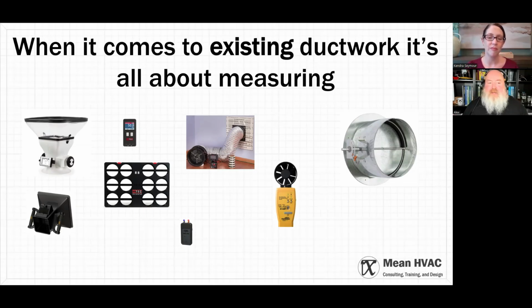Okay, and you can do a halfway deep. This is about a $50 piece of kit that I can use to get a rough idea of what the system's airflow is, based on a chart they published, provided that I clean the blower wheel. It takes some work, but provided I have a nice clean blower wheel and a nice clean coil, I probably can have a good idea how much air is moving through the unit.